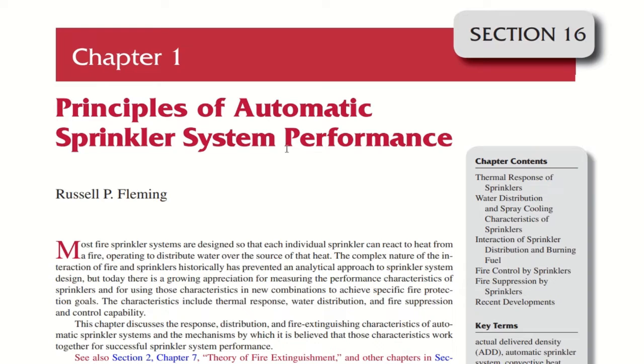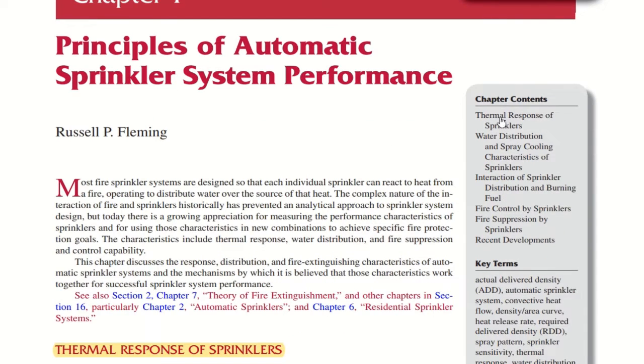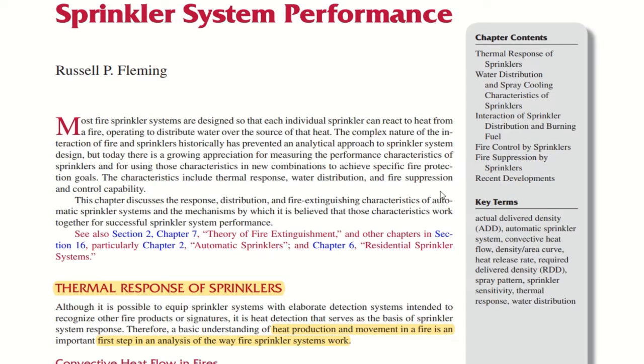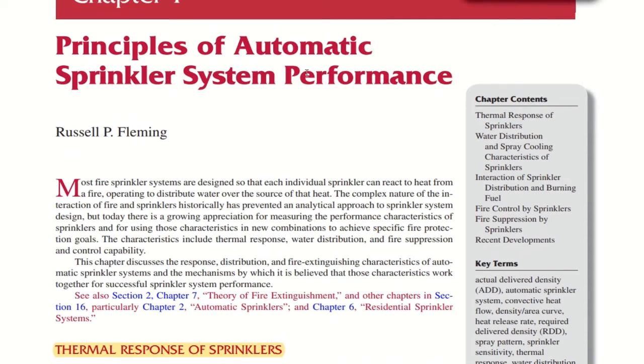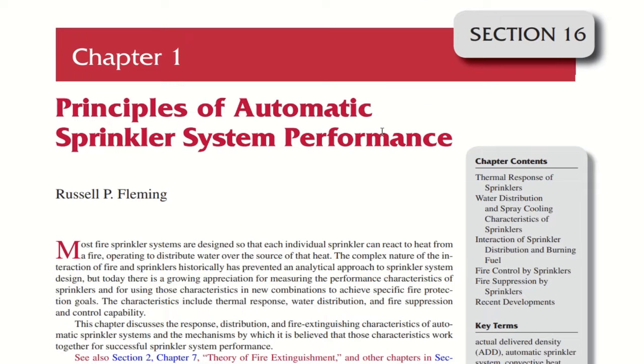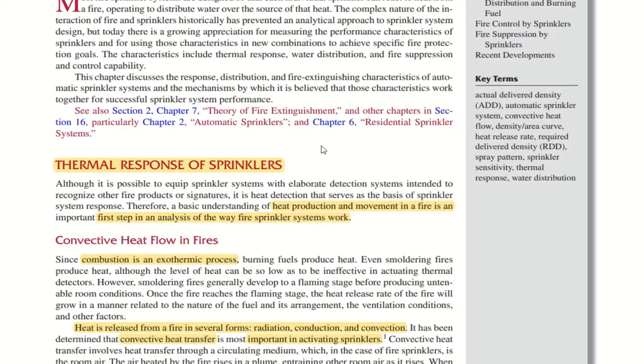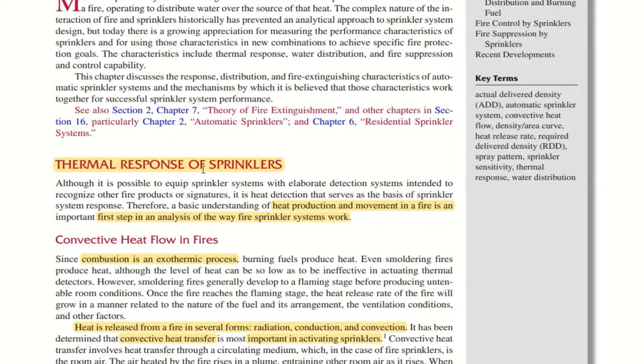Chapter 1 refers to principles of automatic sprinkler system performance. On the right hand side of this fire protection handbook, you can find the topics and the key terms covered in this particular chapter. In principles of automatic sprinkler system performance, you just need to remember that performance means the thermal response characteristics and the spray characteristics of the automatic sprinklers. Keep this in mind. The first topic refers to the thermal response of sprinklers. Basically, we need to understand heat production and movement in a fire, which is the important first step in analyzing the way fire sprinkler systems work.